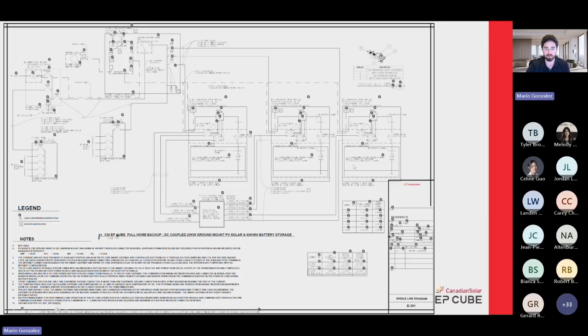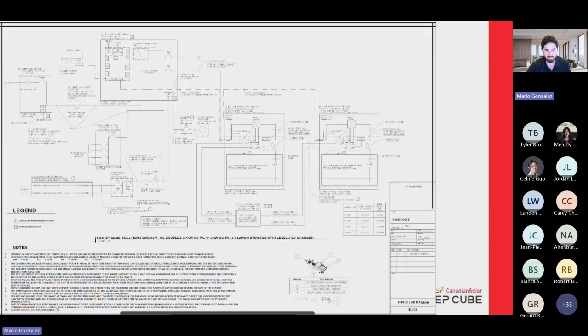This one is basically just showing you the AC coupling and DC coupling configuration. I'll explain it again here. The meter disconnect. Again, you need that disconnect because EP Cube is not service rated, very important. Then you have 2 DC coupled inverters into the gateway. And then basically down here, you have an AC system, in this case Enphase microinverters going to 2 branch circuits, 20 amps, which then go to a main 60 amp disconnect. And ideally, you can use a 40 amp disconnect. It doesn't have to be 60, but in my experience, 60 is easier to get from distributors. So that's why you get the bigger breaker size. And here you have an EV charger, basically.